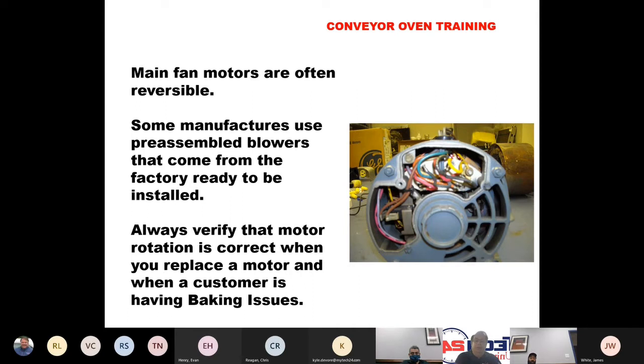So a lot of manufacturers use pre-assembled blowers, and they'll come from the factory ready to be installed. But you always want to verify the rotation is correct when you replace a motor, especially if your customer's having a bake issue. On a motor like this, there'll be a little diagram on your data plate. And on this motor in particular, to reverse direction, we reverse the red and the black wire. It's that simple.